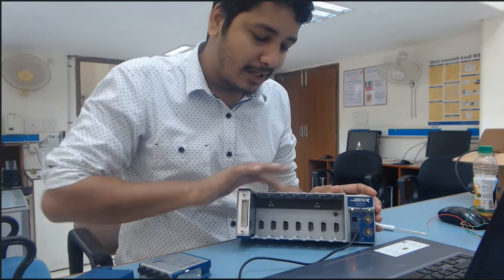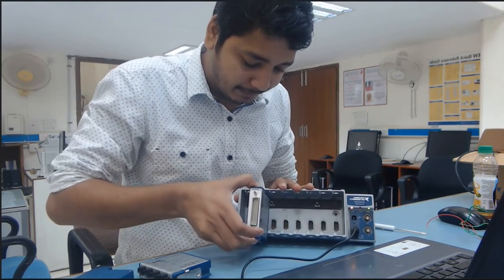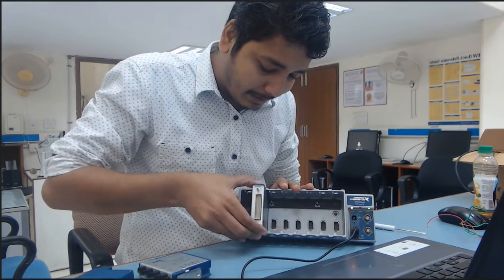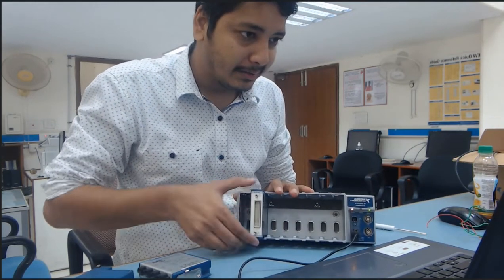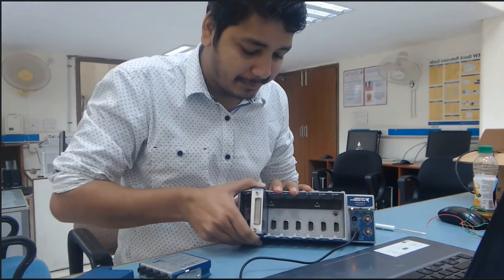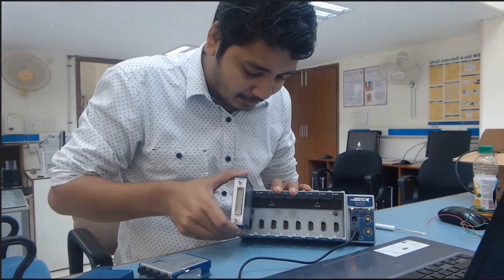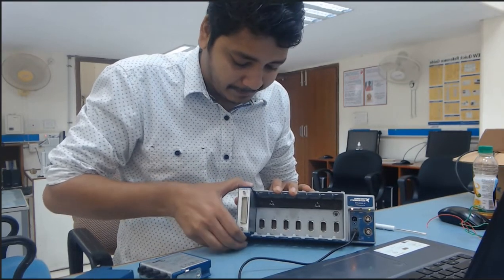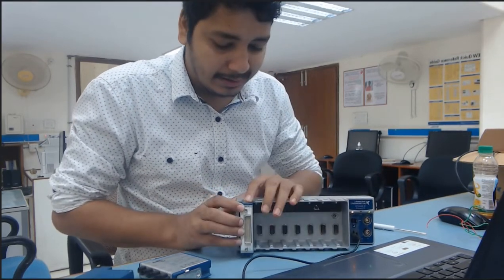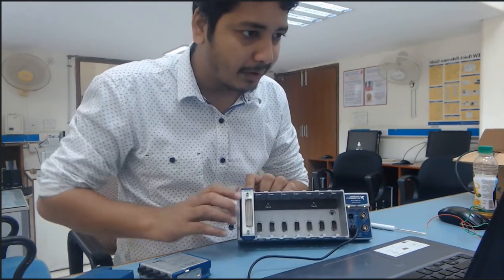You can change the location anytime during runtime — no need to disconnect your chassis from the computer. You can connect or remove this module from your chassis at any time. I have connected one module on location number eight on the NI cDAQ 9178 chassis.